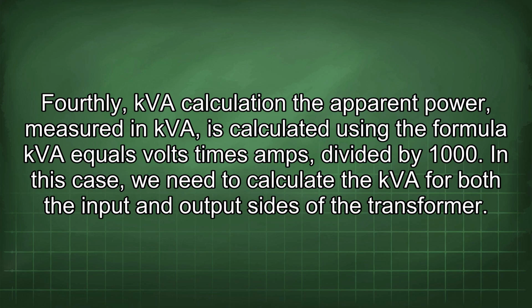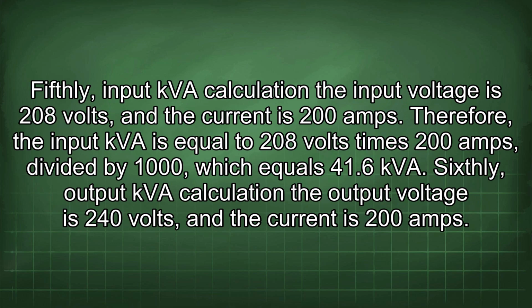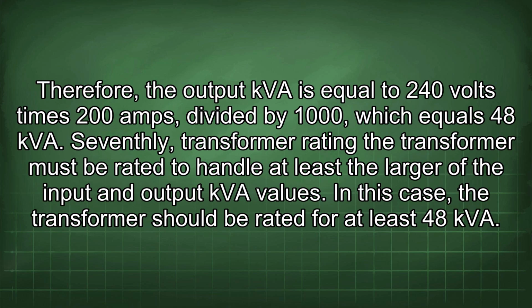Fourthly, kVA calculation. The apparent power, measured in kVA, is calculated using the formula kVA equals volts times amps divided by 1000. In this case, we need to calculate the kVA for both the input and output sides of the transformer. Fifthly, input kVA calculation. The input voltage is 208 volts and the current is 200 amps. Therefore, the input kVA is equal to 208 volts times 200 amps divided by 1000, which equals 41.6 kVA. Sixthly, output kVA calculation. The output voltage is 240 volts and the current is 200 amps. Therefore, the output kVA is equal to 240 volts times 200 amps divided by 1000, which equals 48 kVA.